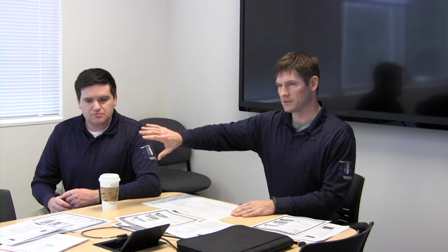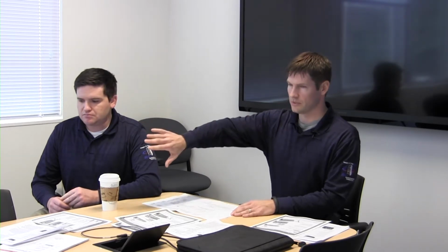So the fan coil, my mistake, I don't have paperwork for it, but luckily it is a fan and a coil. So when you remove compressors, things get simple. These are console unit fan coils. So it's a unit that goes against the wall. It returns up through the bottom, goes through a filter, goes through a water coil, and then comes out through the fan. And I think this is just heating.